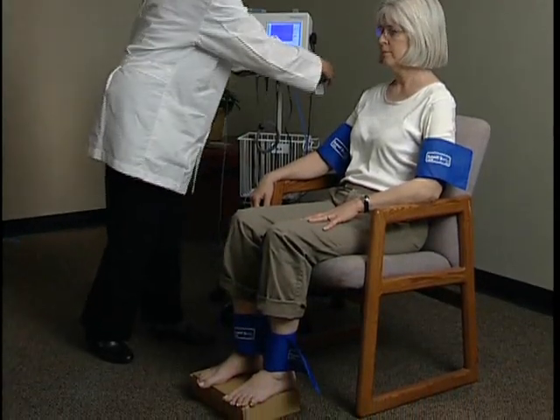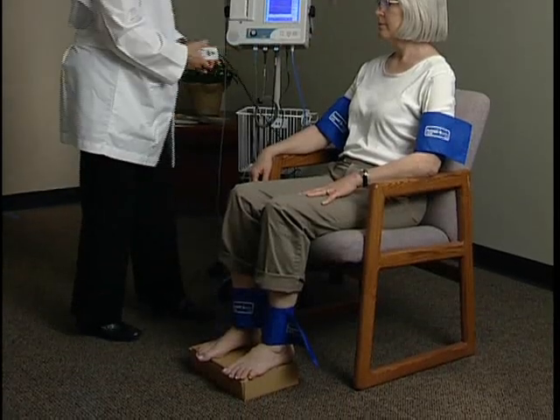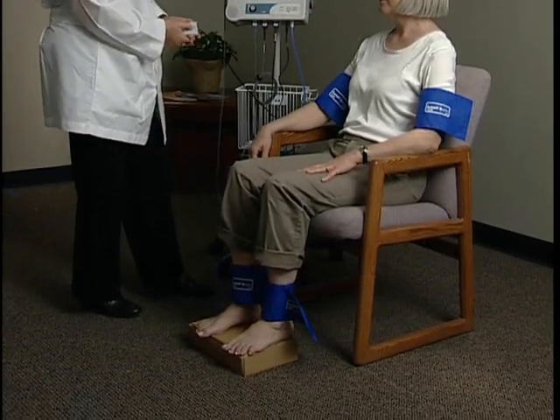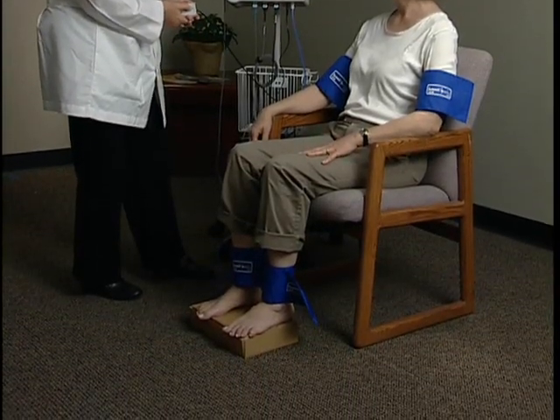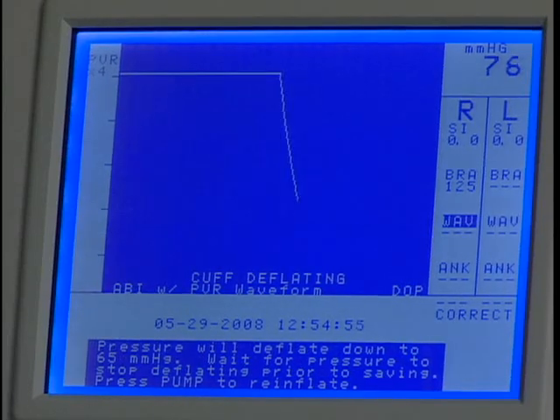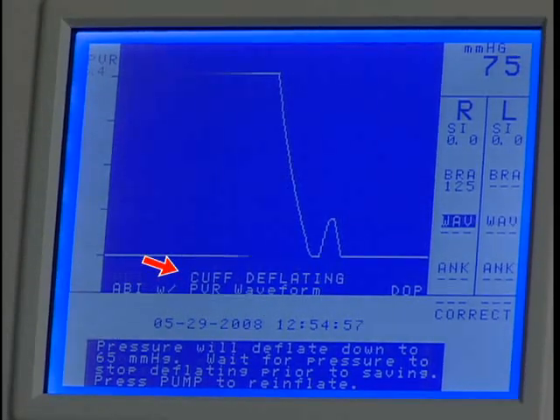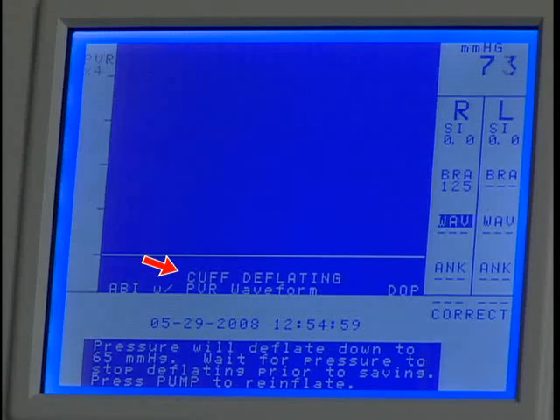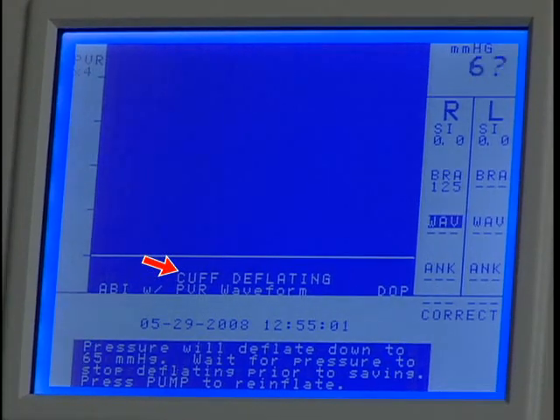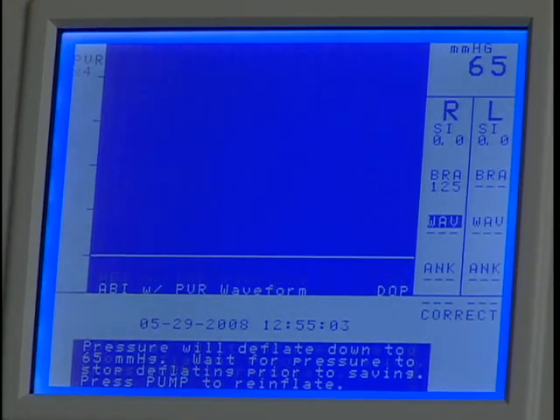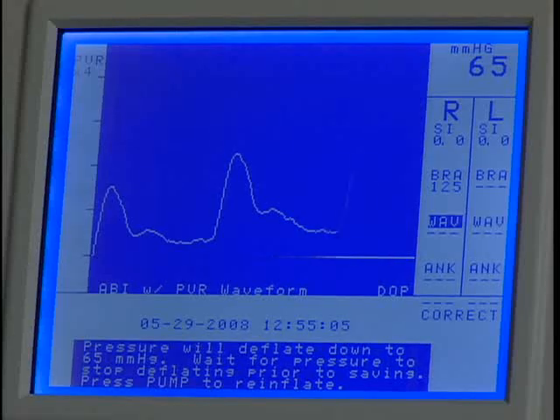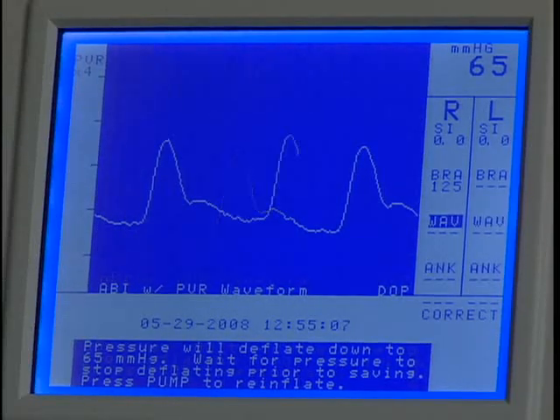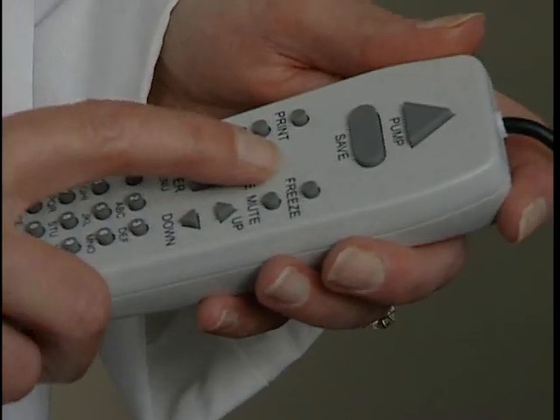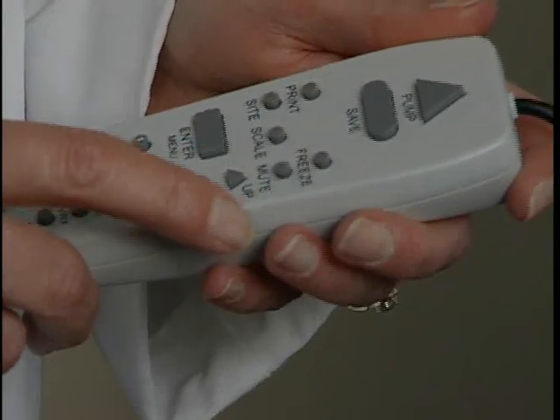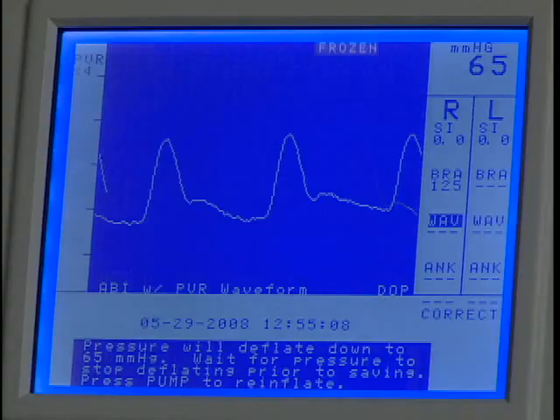Move the hose to the ankle cuff and press and hold pump to inflate the cuff to 75 millimeters of mercury. Release when the inflation automatically stops. Pressure will deflate to 65 millimeters of mercury for optimum PVR. Wait for the cuff deflating message on the display to disappear. If needed, use the scale key to optimize the waveform. After the waveform stabilizes, press Freeze.